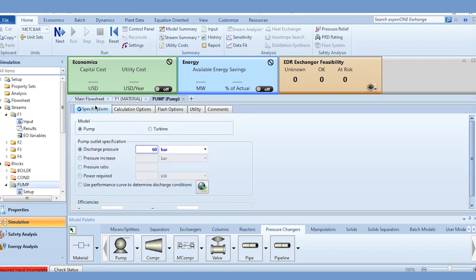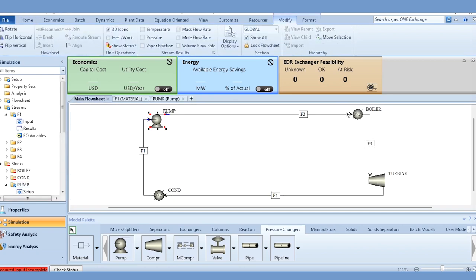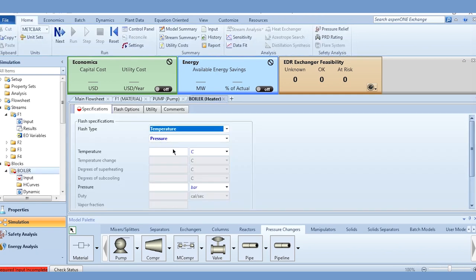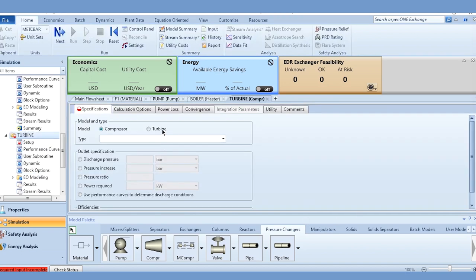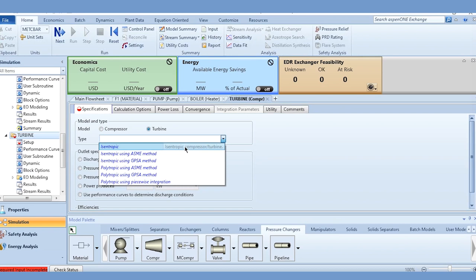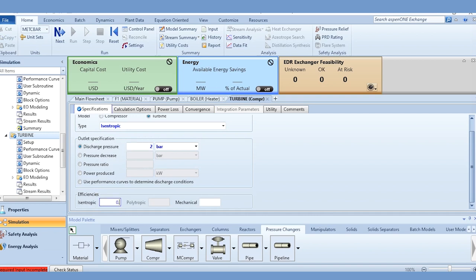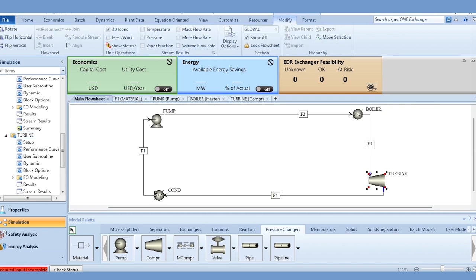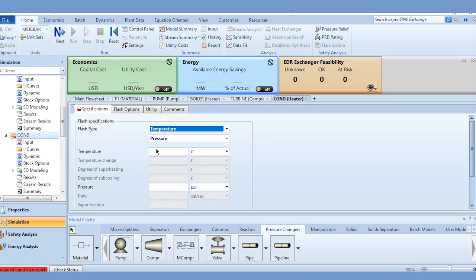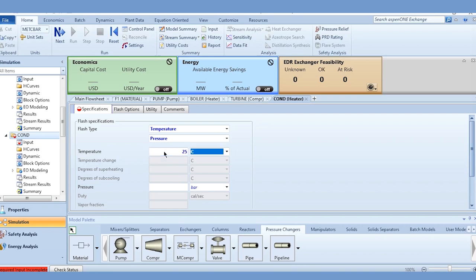Going to the pump, the discharge pressure is 60 bar. Then going to the boiler — 600 degrees centigrade with a pressure drop of 0.1 bar. Going to the turbine module, the isentropic discharge pressure is 2 bar and the isentropic efficiency is 0.72. Then going to the condenser — its properties should remain the same as the feed due to the recycling process: 25 degrees centigrade, 1 bar.